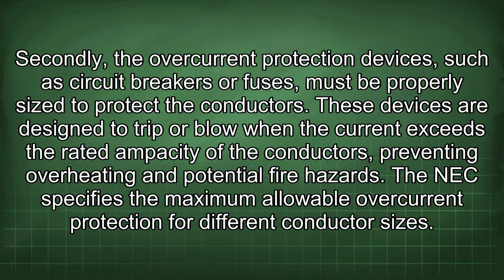Secondly, the overcurrent protection devices, such as circuit breakers or fuses, must be properly sized to protect the conductors. These devices are designed to trip or blow when the current exceeds the rated ampacity of the conductors, preventing overheating and potential fire hazards. The NEC specifies the maximum allowable overcurrent protection for different conductor sizes.